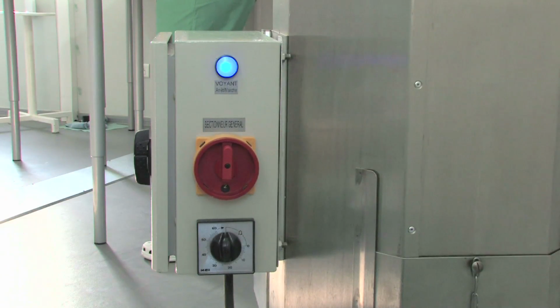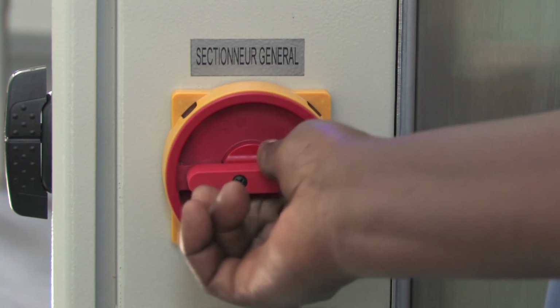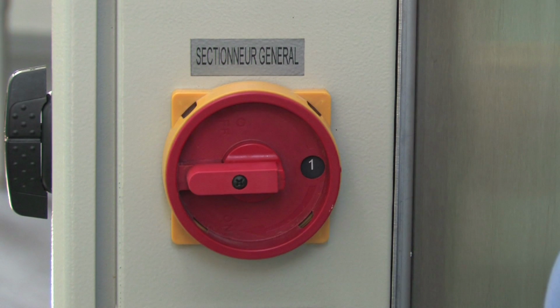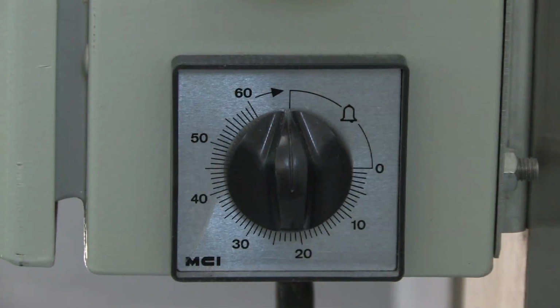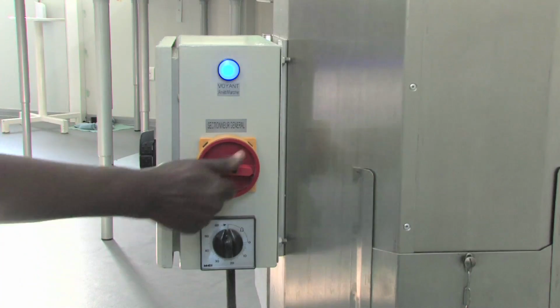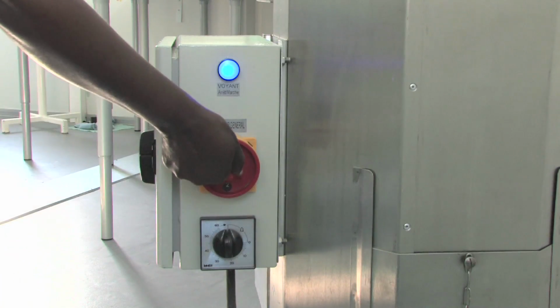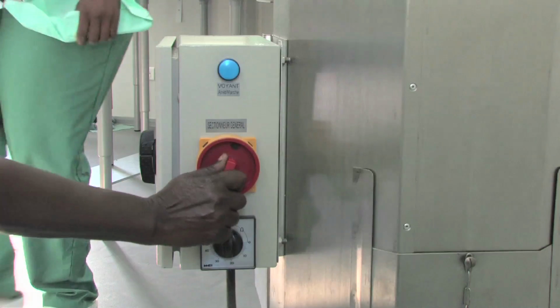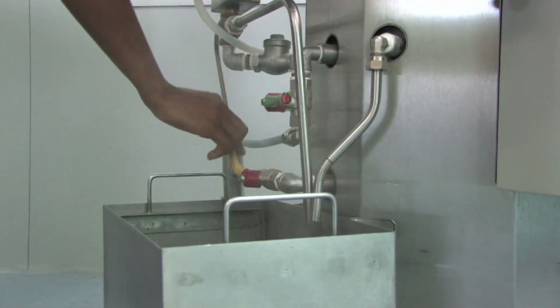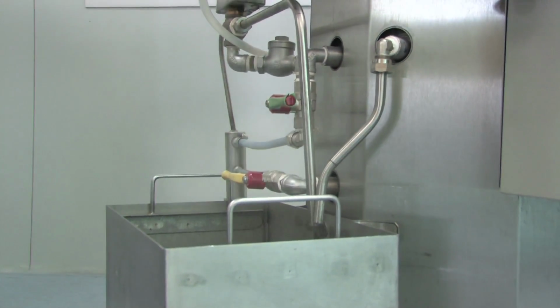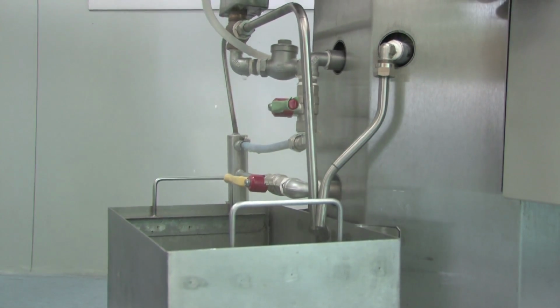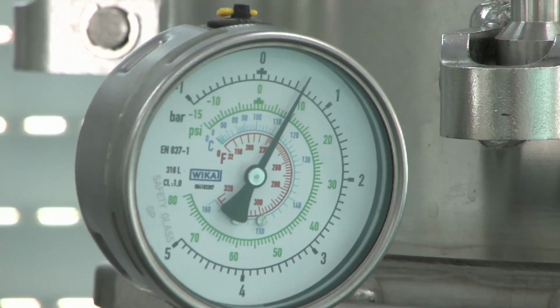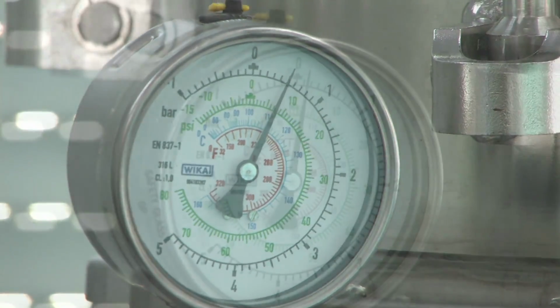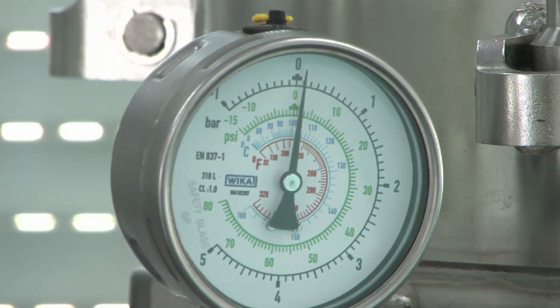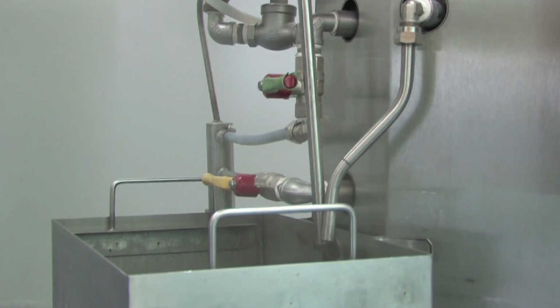To keep the pressure constant at 1 or 2 bars depending on the cycle chosen, reduce the heat level when necessary by lowering the heat to position 1 or 2. 5. When the sterilization plateau is finished, turn off the heat by setting it to position 0. Open the yellow valve to drain the boiling water remaining in the autoclave tank. Be careful not to get splashed by the boiling water. Let the pressure drop to 0.1 bars. Then close the yellow valve.